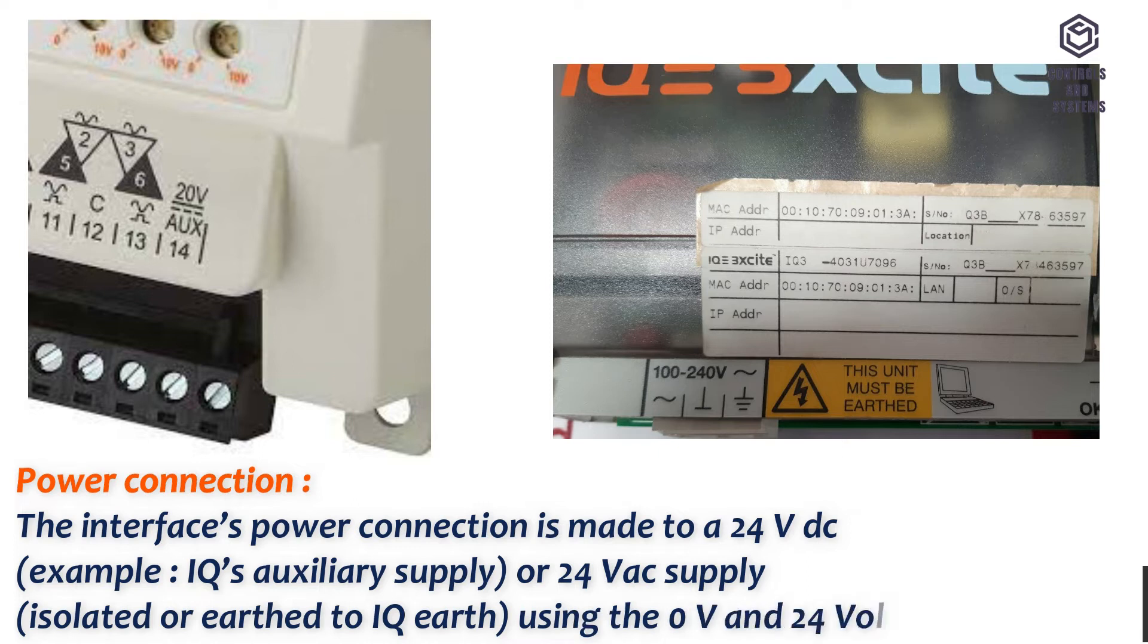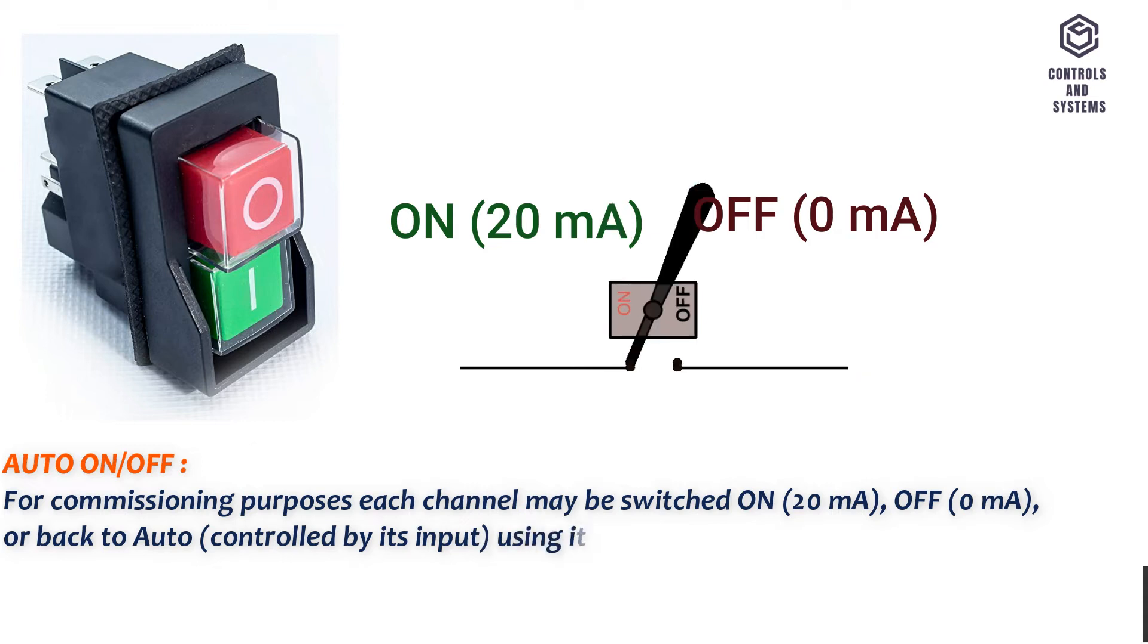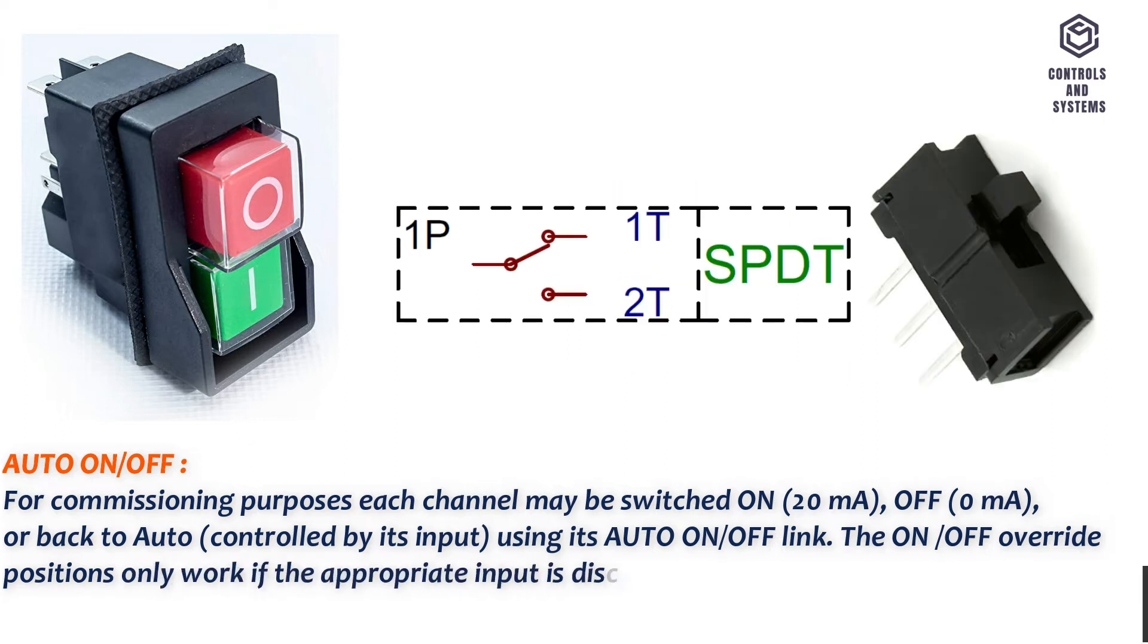Auto on/off: For commissioning purposes each channel may be switched on 20 milliamps, off 0 milliamps, or back to auto controlled by its input, using its auto on/off link. The on/off override positions only work if the appropriate input is disconnected.